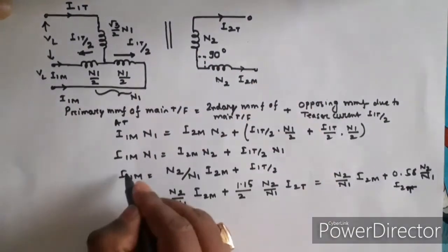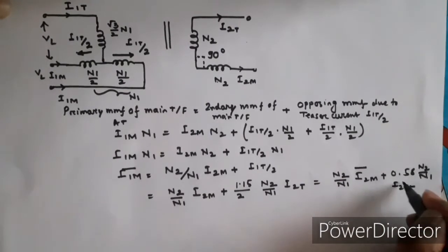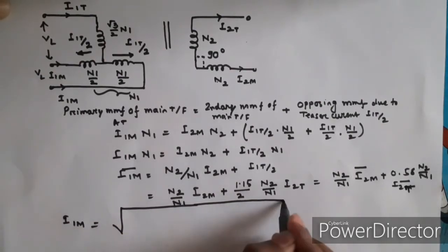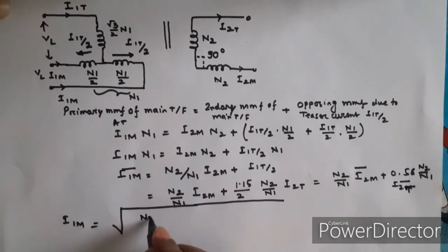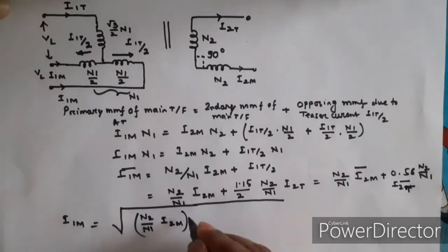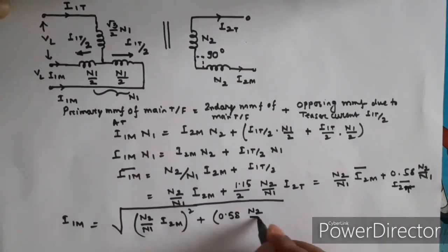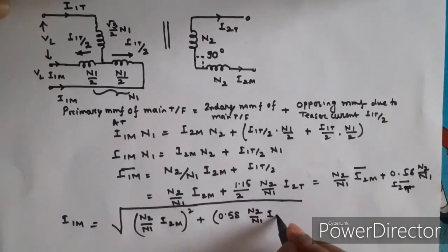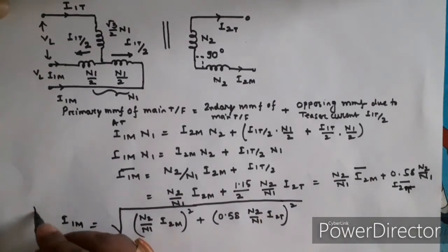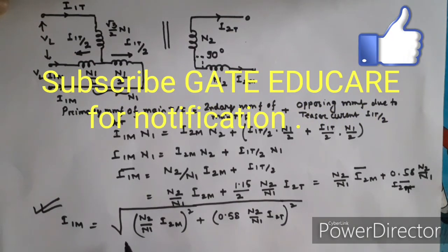Since the phase displacement is 90 degrees, all these quantities are vector quantities. Therefore, the main transformer primary current I1M is the vector sum: I1M = sqrt[ (N2/N1 × I2M)² + (0.58 × N2/N1 × I2T)² ]. You have to remember this equation — numericals based on this equation can come in your exam. This is the end of Scott Connection.